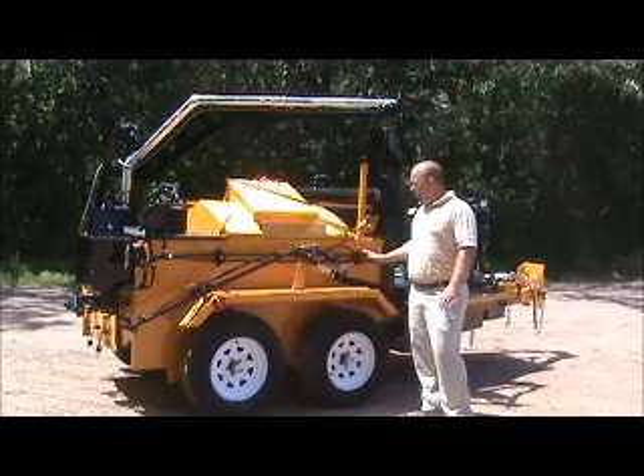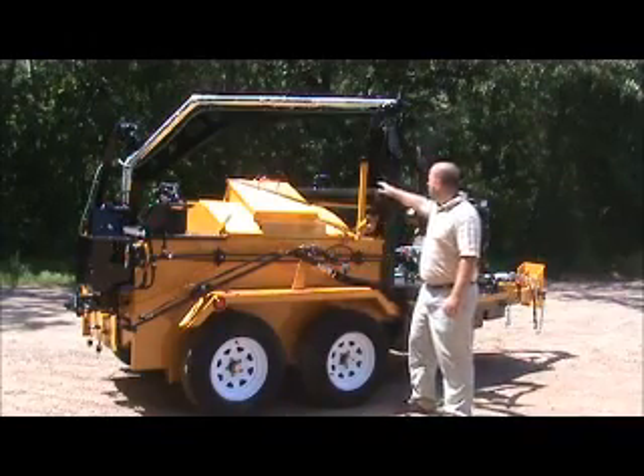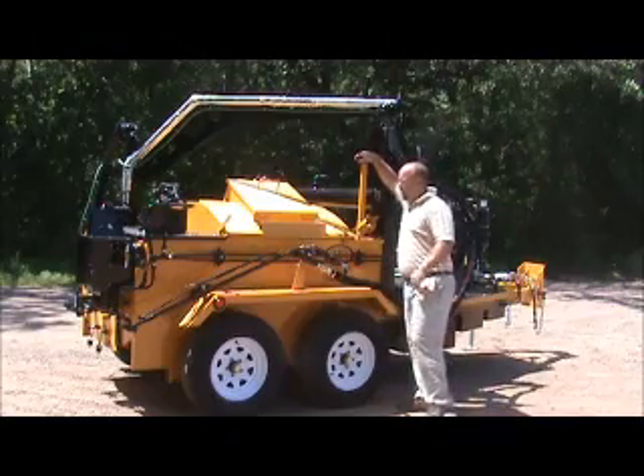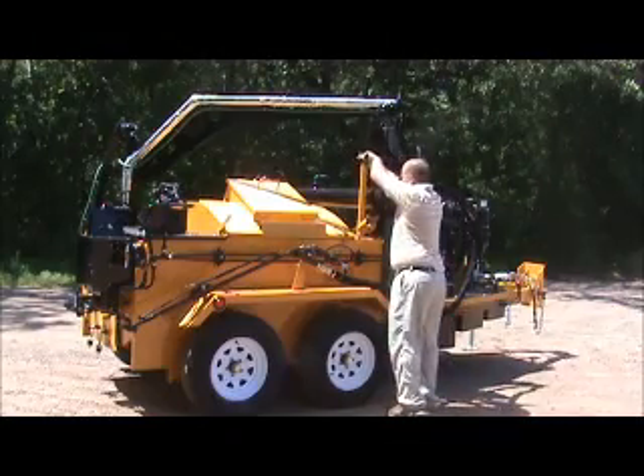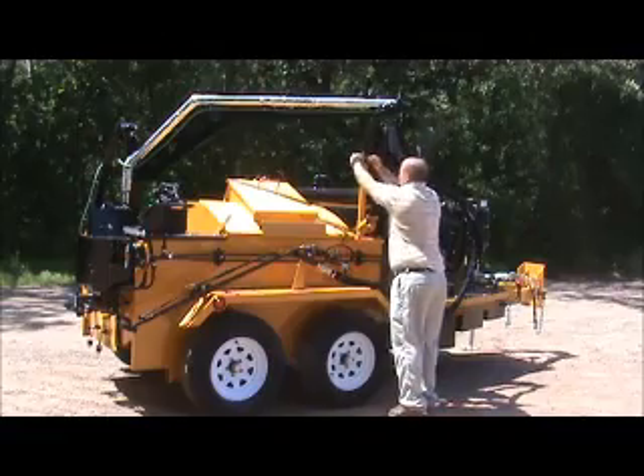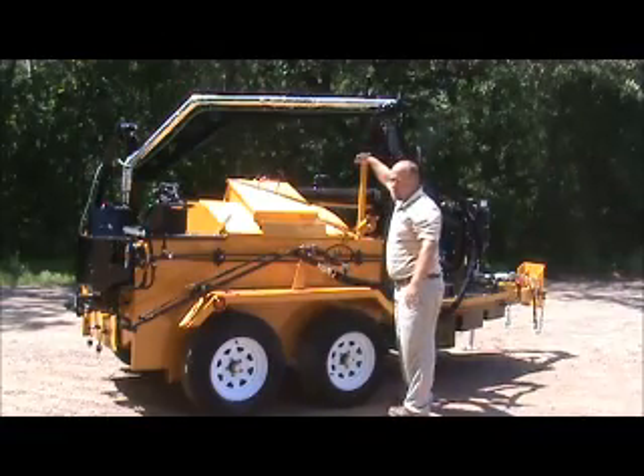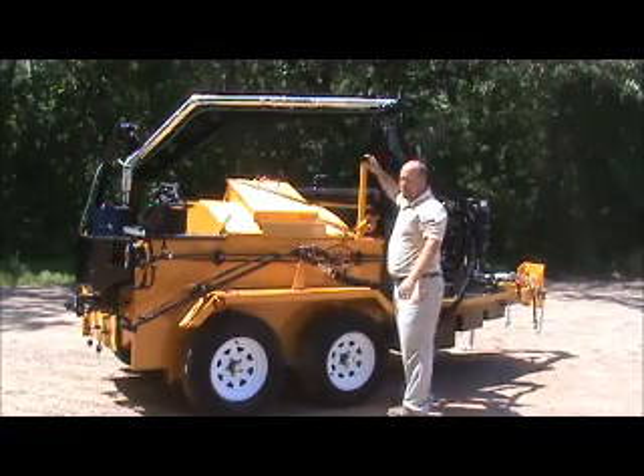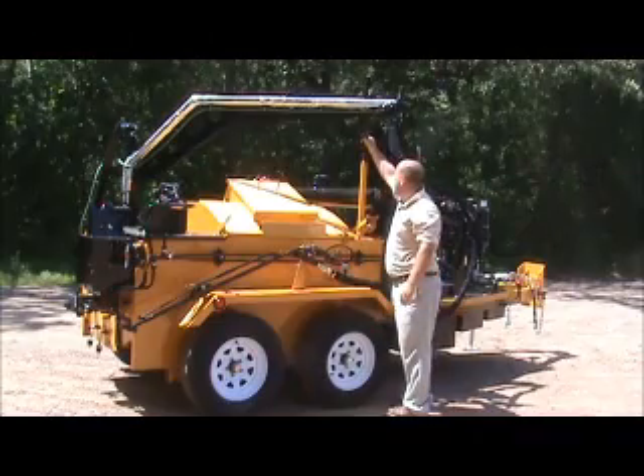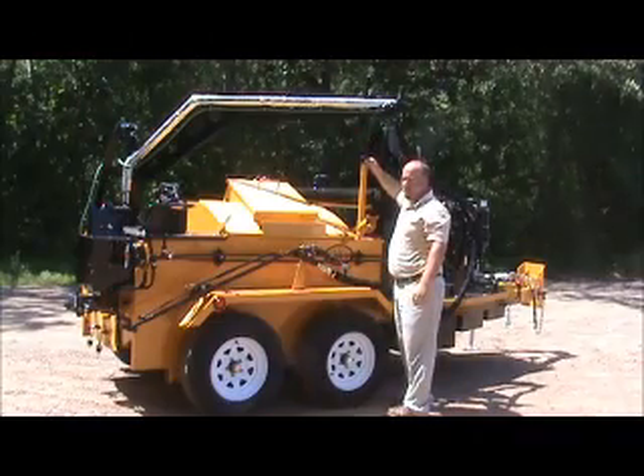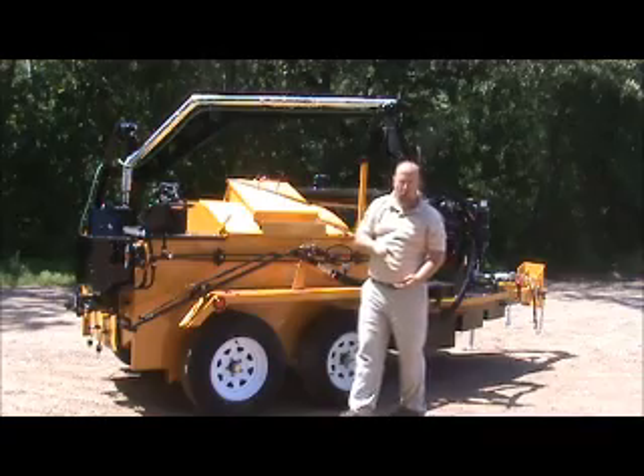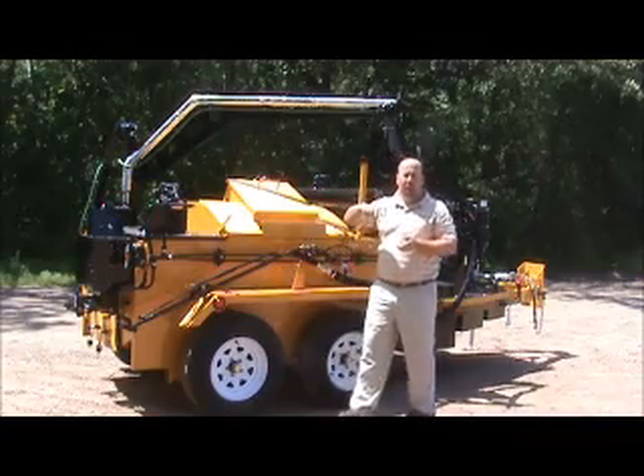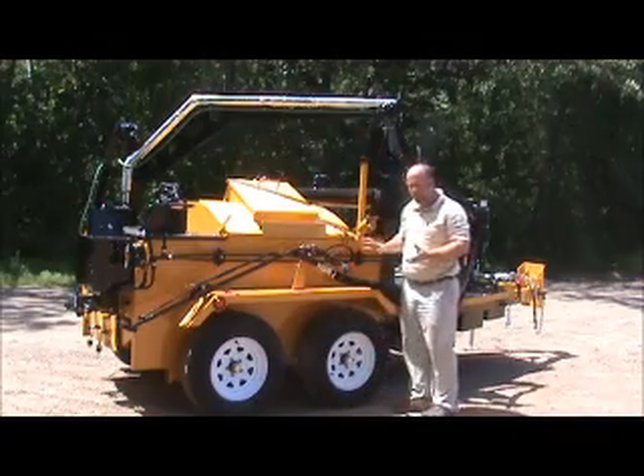We're going to pull the wand off in just a minute. I do want to show you, we've got a dipstick here. This is for our heating oil. You can check this either when it's hot or cold. If you check it when it's hot, just use caution because it's very hot. There is a dipstick. On the dipstick, there's 4 marks. There's 2 marks low, there's 2 marks high. The high marks are if you're checking this when it's hot.